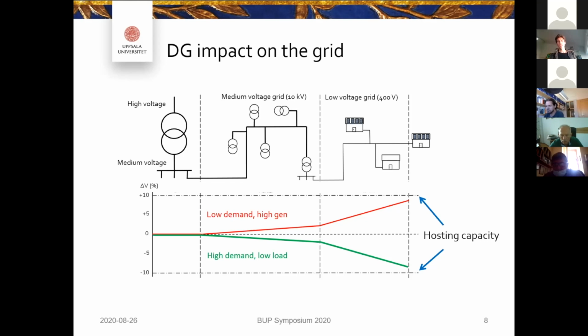In this project we looked at PV parks connected to medium voltage substations, focusing on the overvoltage problem on the medium voltage side, not the low voltage. To have some slack on the customer side, we decided, after talking to the grid operator, that 3% is a conservative but good limit to give some slack to the consumer.